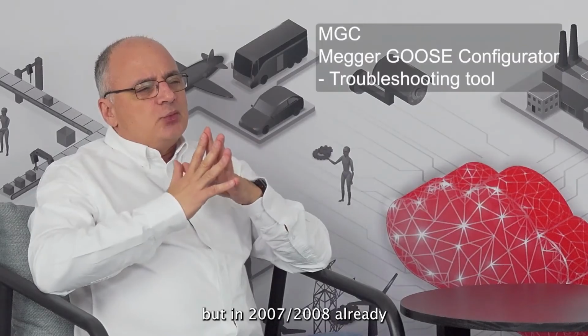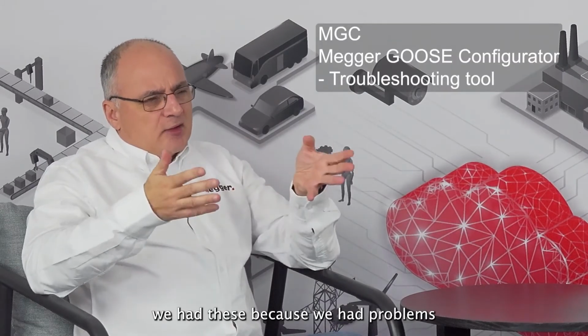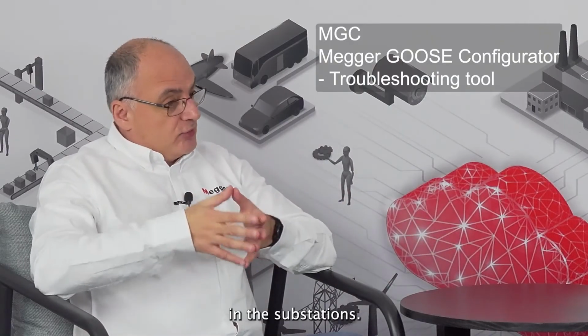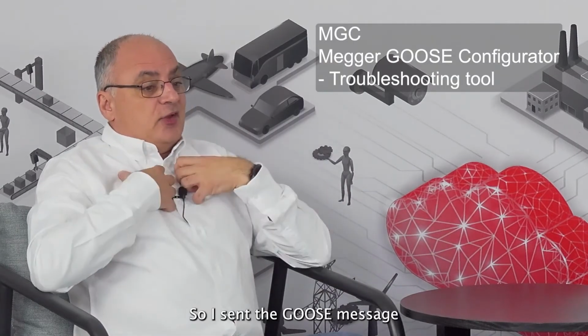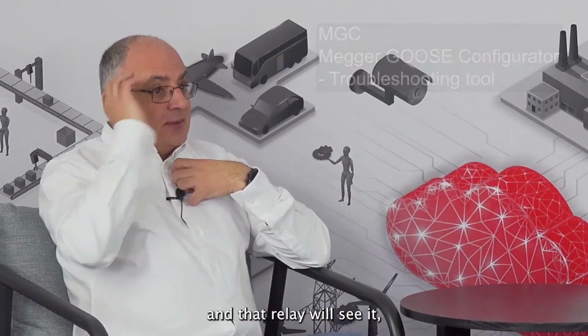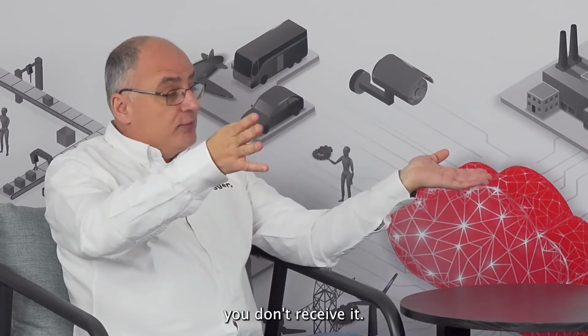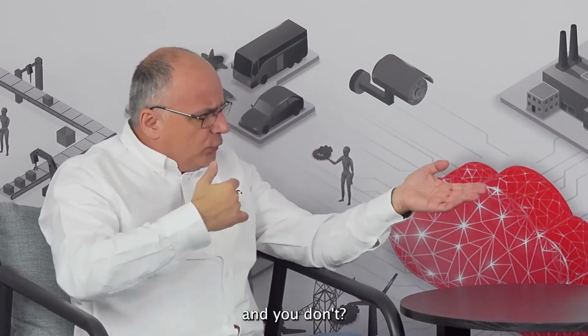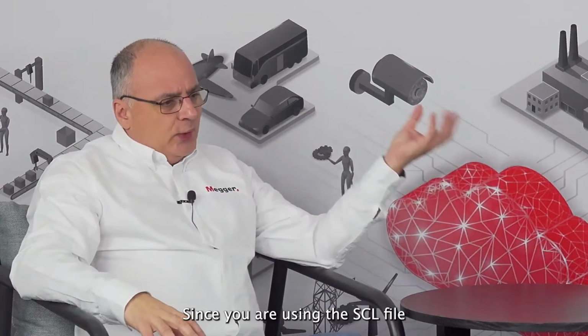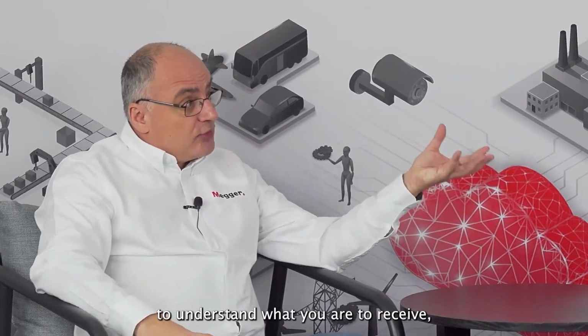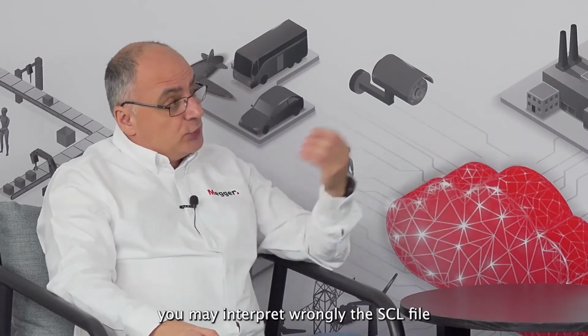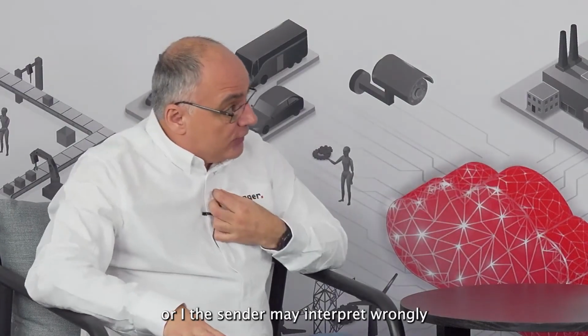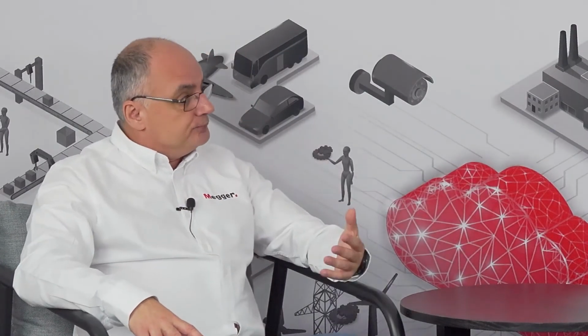2009 was when the final product was available, MGC, but already in 2007, 2008 we had this, because we had problems in the substations. We had interoperability problems in the substations. So I send a GOOSE message, and that relay will see it. You don't receive it. Why is one relay receiving my message and you don't? Since you are using the SCL file to understand what you have to receive, you may interpret the SCL file wrongly, or the sender may interpret the SCL file wrongly.